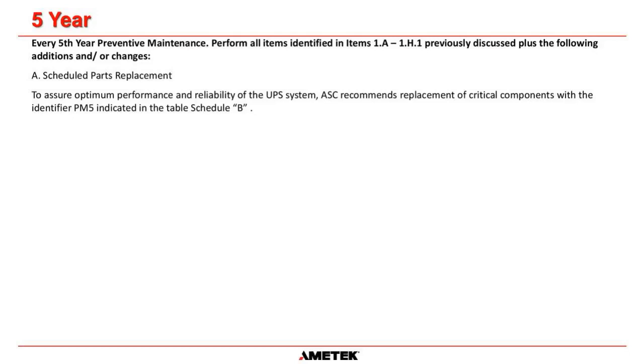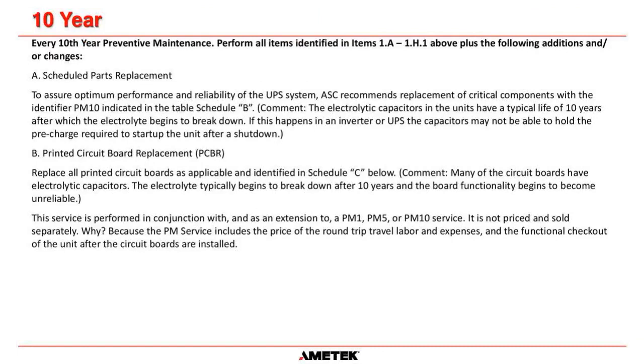Now, every 5 years, we do exactly what we just said for an annual, and then there are some additional parts that are recommended, which are in the table Schedule B, which I'll get to in just a moment. And then 10 years is our most invasive PM. To ensure performance and reliability, we replace all of the AC capacitors, the DC capacitors, the fans, the relays, and all of the PCBs. And I'll explain why in a little bit, but it's mainly down to DC electrolytic capacitors. They have a designed life from the manufacturer, and we calculate what that designed life is, and we say, okay, after 10 years, it goes past that design life, and therefore you have to replace them.